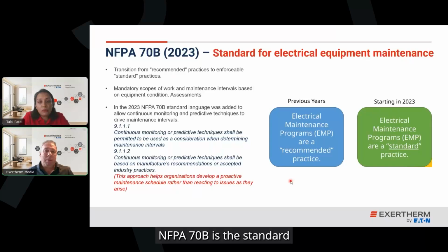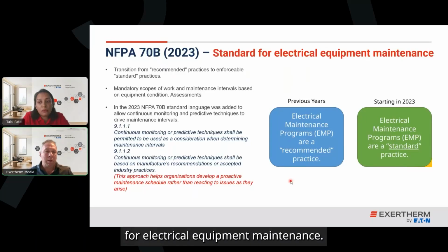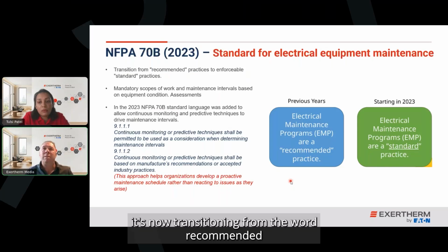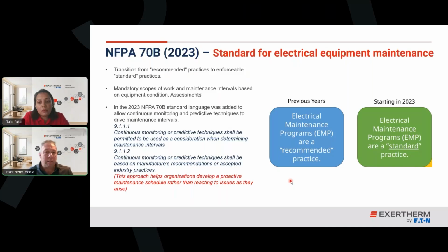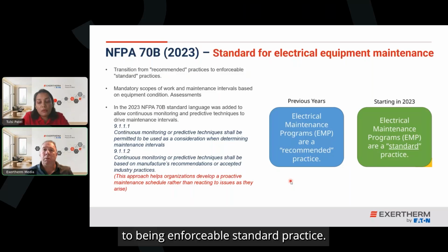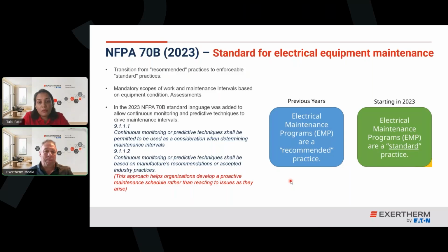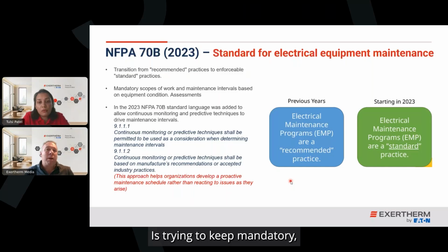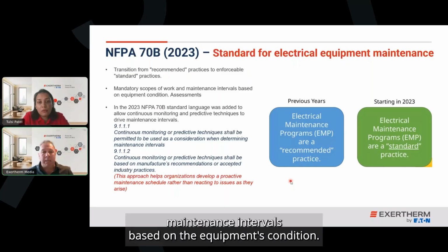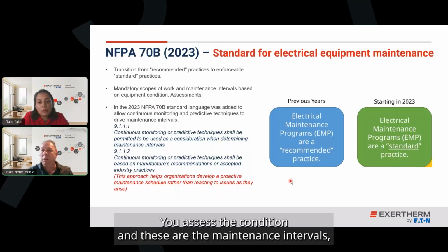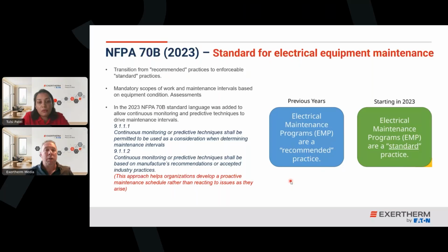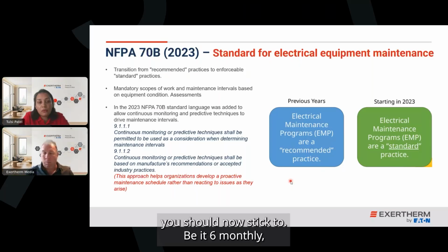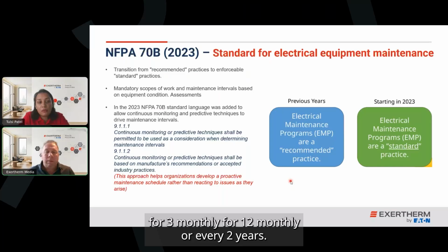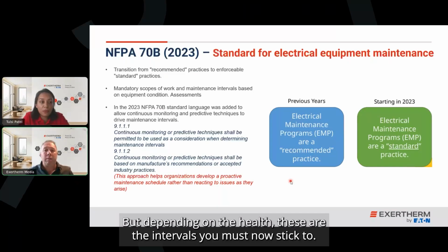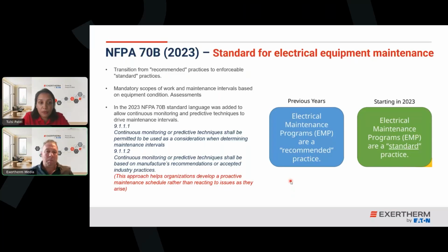NFPA 70B, it's the standard for electrical equipment maintenance. And as I mentioned a couple of slides ago, it's now transitioning from the word recommended to being enforceable standard practice. It's trying to give mandatory maintenance intervals based on the equipment's condition. You assess the condition, and these are the maintenance intervals you should now stick to, be it 6 monthly, 3 monthly, 12 monthly, every 2 years. But depending on the health, these are the intervals you must now stick to.